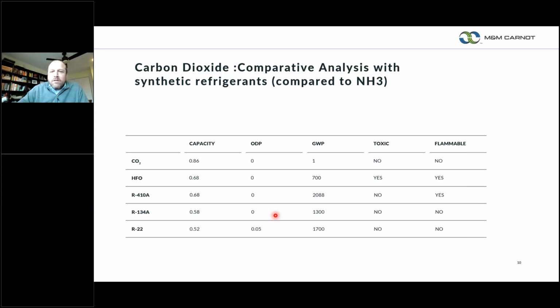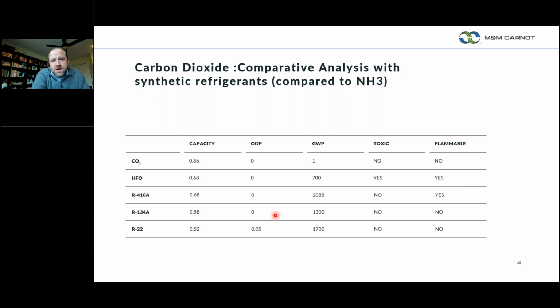So that is where we are as a company specializing in natural refrigerants. Specifically, our data center cooling equipment uses carbon dioxide. I put this chart up to show you some of the properties of CO2 compared to some of the other synthetic refrigerants that are out there. This chart is compared to ammonia. Ammonia is another natural refrigerant, but it can be fairly toxic. If you're deploying this in a data center space and you have an ammonia leak, that would be a concern, whereas CO2 isn't toxic like ammonia or the other synthetic refrigerants could be.